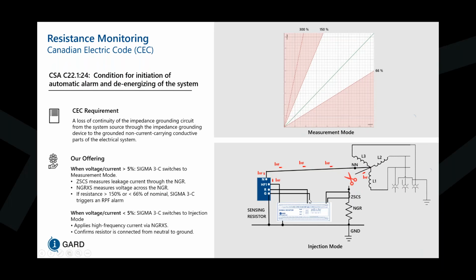Now, another mode of our relay is measurement mode, where if we have a neutral voltage and a neutral current, we back calculate the resistance using Ohm's law and compare it to the resistance on the nameplate. If it's within the band of 66% to 150%, we're still in the clear, but anything beyond the boundaries in the red zone is considered an NGR fault.